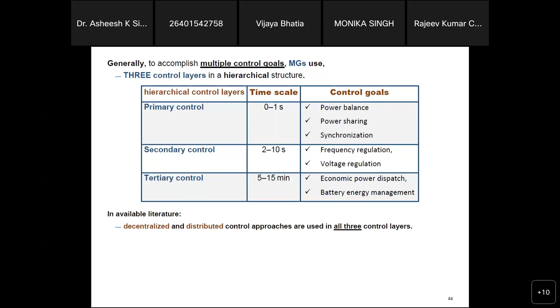This is a summary from another recent paper from 2021. It indicates that primary control stabilizes the voltage and frequency of the microgrid by implementing fast-acting voltage and current control loops, with an operation cycle time in milliseconds. Secondary control compensates the residual deviations of omega and voltage after primary control executes, with a cycle time of milliseconds to seconds. Tertiary control operates on a cycle time of minutes to hours, ensuring optimal power flow and economic dispatch, regulating active and reactive power, and maintaining system synchronization.